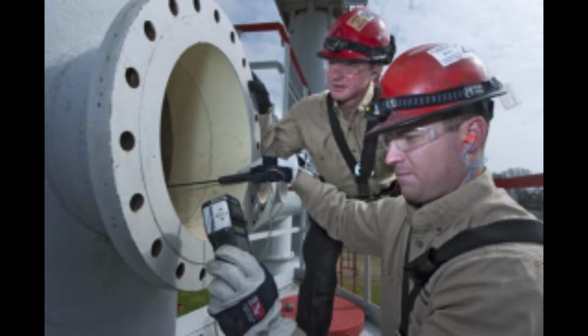E, if after reventilating the detector alarm does not alarm, then complete the confined space entry permit and proceed with entry operations. F, if after reventilating the detector still alarms, call for a second detector and notify your foreman. The second detector may be used to recheck the manhole.